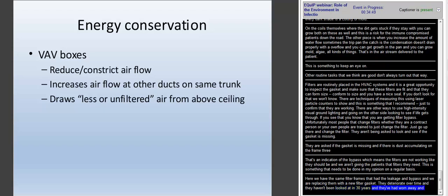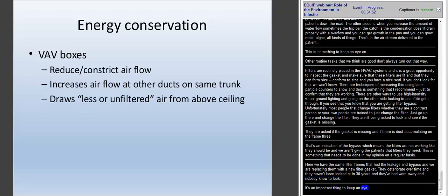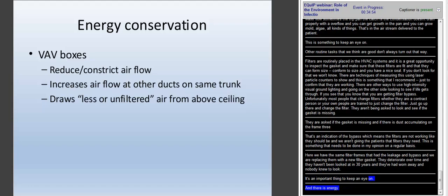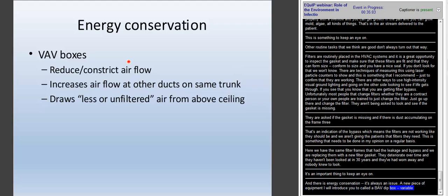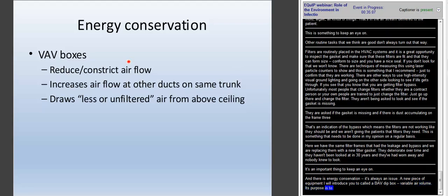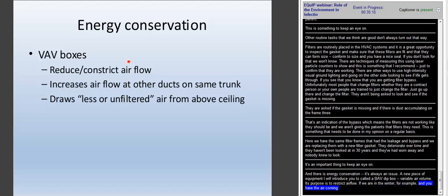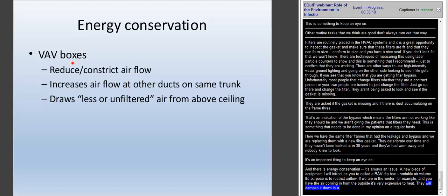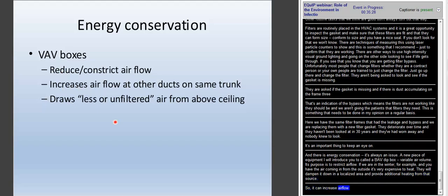Then there's energy conservation, which is pretty much always an issue for me. There's a new piece of equipment I'm going to introduce you to called a VAV box. It stands for Variable Air Volume Box. And its purpose is to restrict airflow. If we're in winter, for example, and you have that cold air coming in from the outside, it's very expensive to heat. It will dampen it down in a localized area, and you'll provide additional heating from that source. So it can increase airflow to other ducts if one of them goes off, and that can be a potential issue.